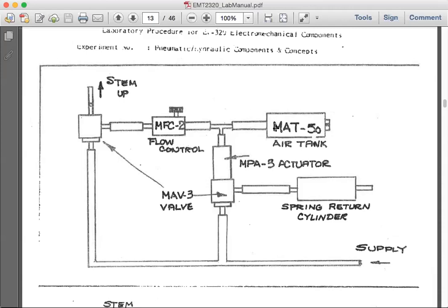the extra volume from the tank, because as long as there is still pressure remaining above 20 psi, this actuator is not deactivated. So this extra volume creates a time delay for longer activation of the actuator, so the piston remains out, extended beyond the activation of the stem.